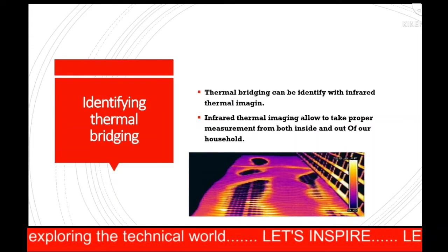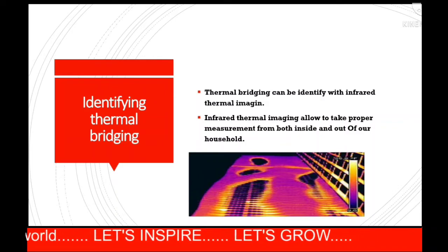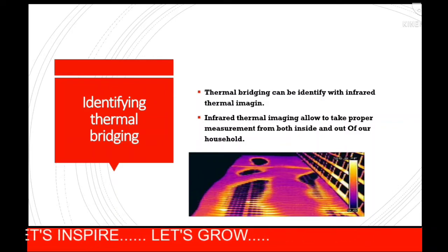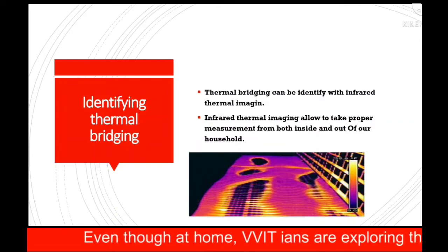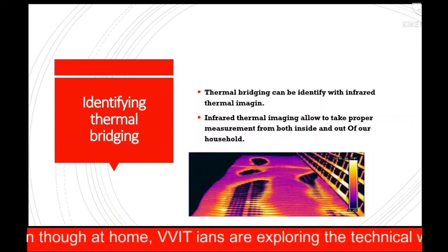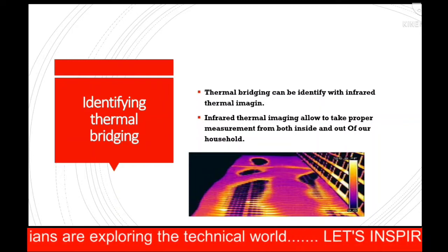Identifying thermal bridges. Surveying a building for thermal bridging is performed using passive infrared thermography. Infrared thermography of a building can allow thermal signatures that indicate heat leaks. Infrared thermography detects thermal abnormalities that are linked to the movement of fluid through building elements, highlighting the variations in the thermal properties of the material that correspondingly cause a major change in the temperature.